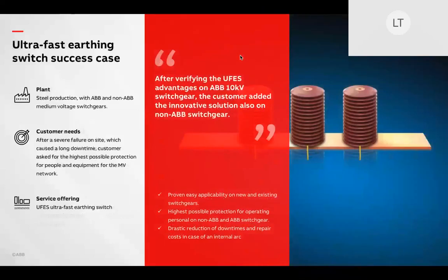This next example is from a steel plant with a combination of both ABB and non-ABB medium voltage switchgear. In this request, the customer had a severe failure on site that caused a plant-wide shutdown for an extended period of time. The customer requested from ABB the highest possible protection for his people and assets on his medium voltage network.